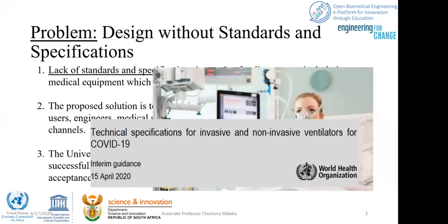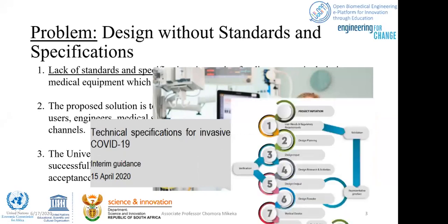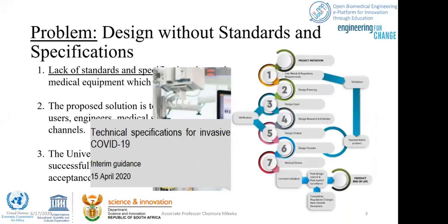Regarding breathing aid devices such as ventilators and CPAP machines, the World Health Organization has developed technical specifications as minimum guidelines for both invasive and non-invasive types. These have been digested, customized, and supplemented with additional engineering specifications to produce a comprehensive list of specs for breathing aid devices, which has attracted global interest.